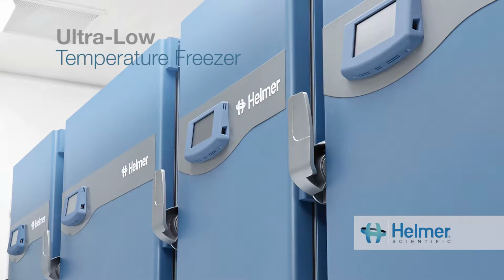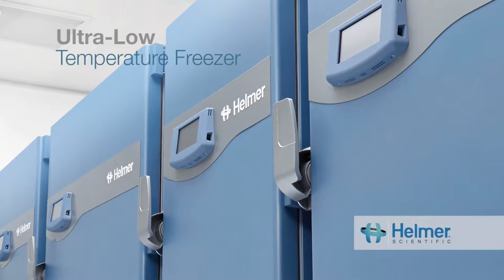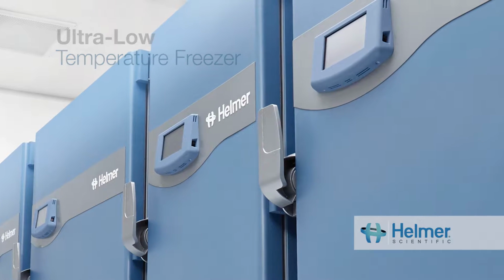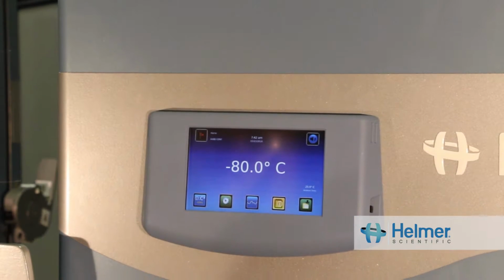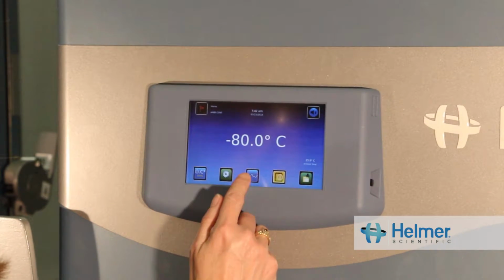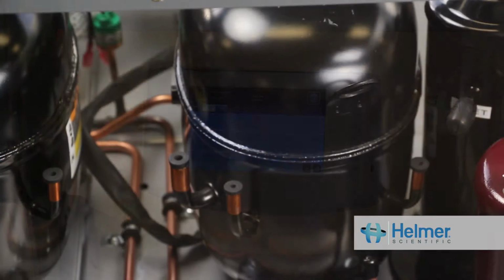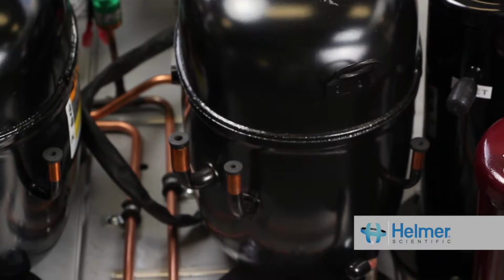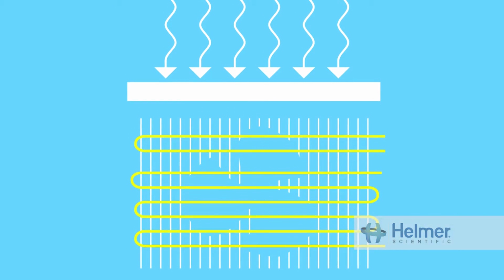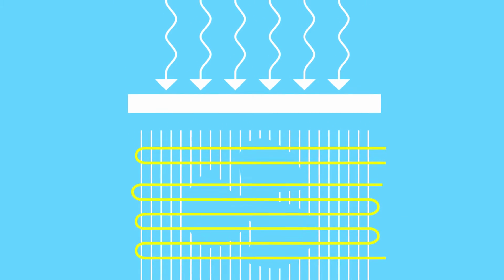Here at Helmer Scientific, we're pleased to show you our ultra-low freezer and to talk about why cooling matters. One of the most important concepts in developing a reliable ultra-low freezer is optimizing the refrigeration system to protect the compressor. By providing maximum heat exchange and developing an exclusive approach to oil management, Helmer has designed a system that reduces stress on the compressor, maximizing reliable performance.